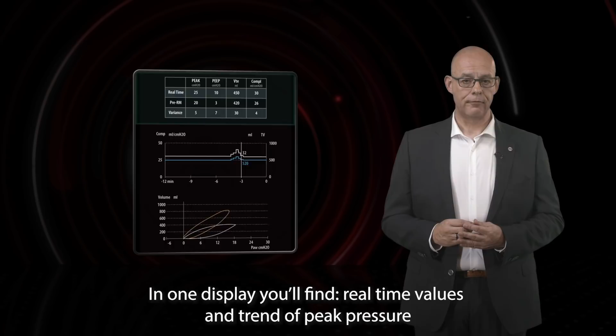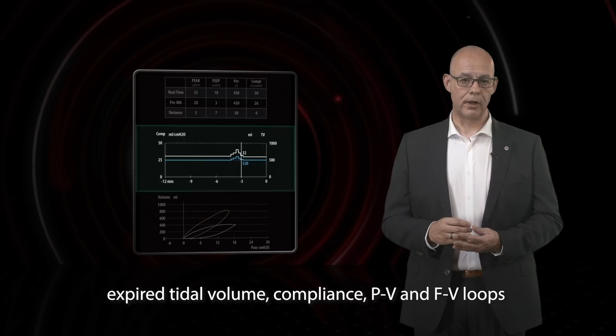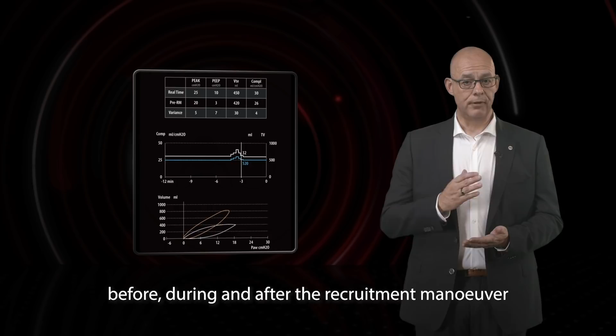In one display you will find real-time values and trend of peak pressure, expired tidal volume, compliance, pressure volume and flow volume loops before, during and after the recruitment maneuver. To summarize, with these tools we can really optimize and customize the ventilation settings for each individual patient. Again, providing more safety for the patient at all stages of the anesthesia procedure and surgical intervention.